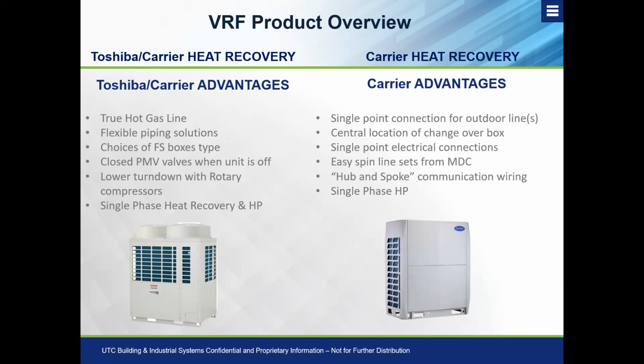We have lower turn down with rotary compressors, which is one of the reasons why the rotary compressors are utilized with these PMVs that are shut 100%. They are more efficient at lower frequencies with our rotary style compressors. And we have single phase heat recovery and heat pump options depending on residential and low commercial application.